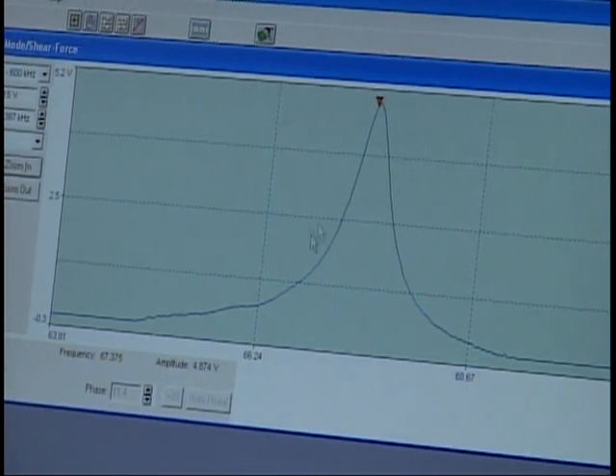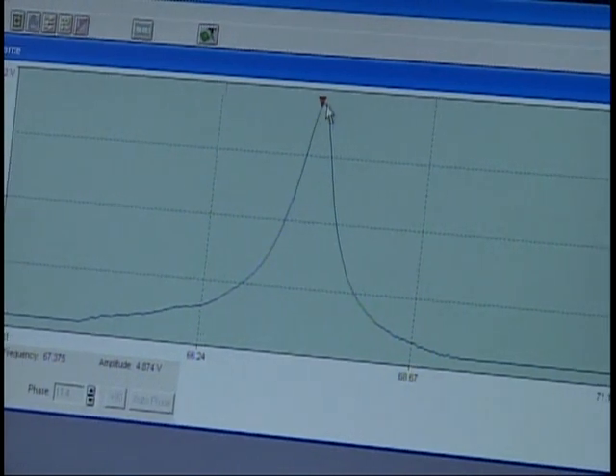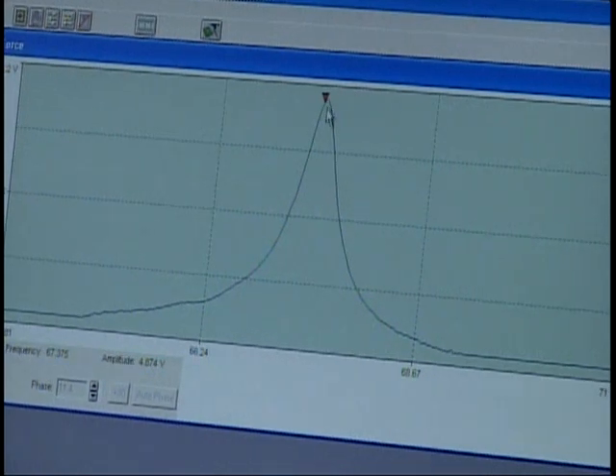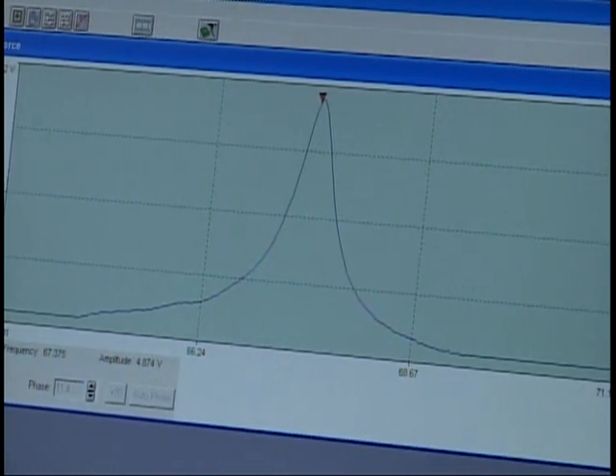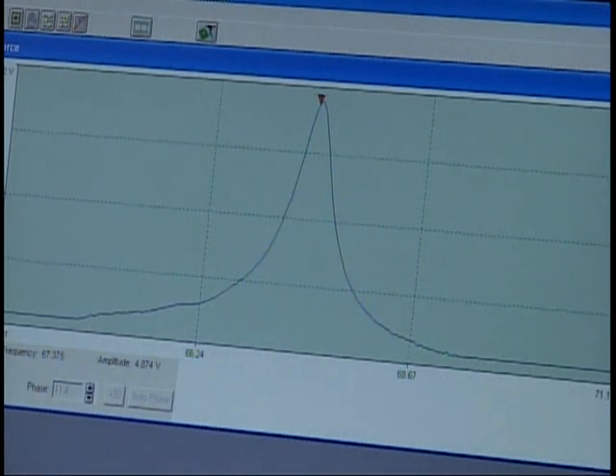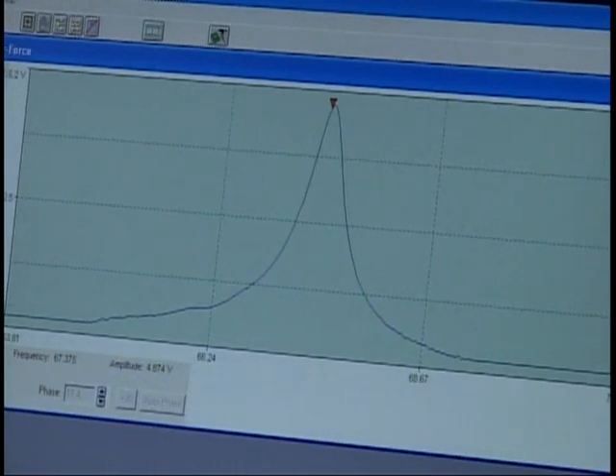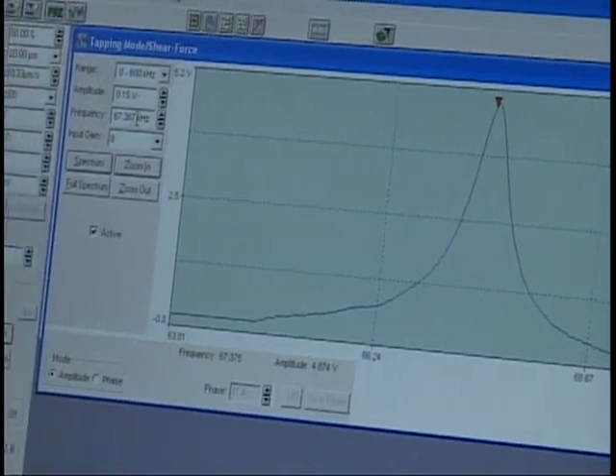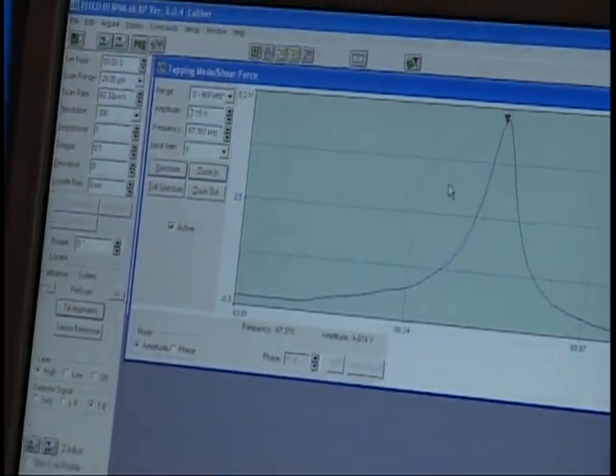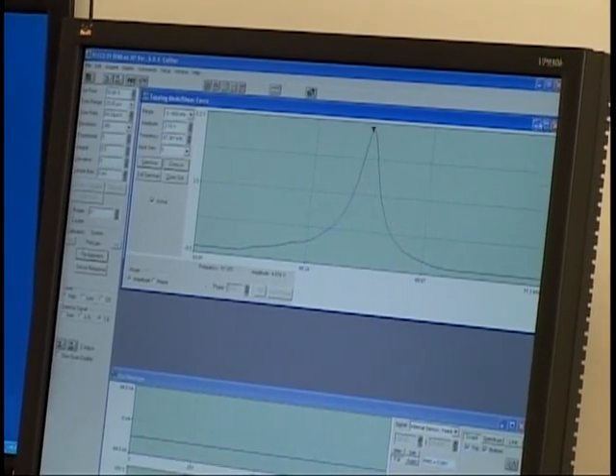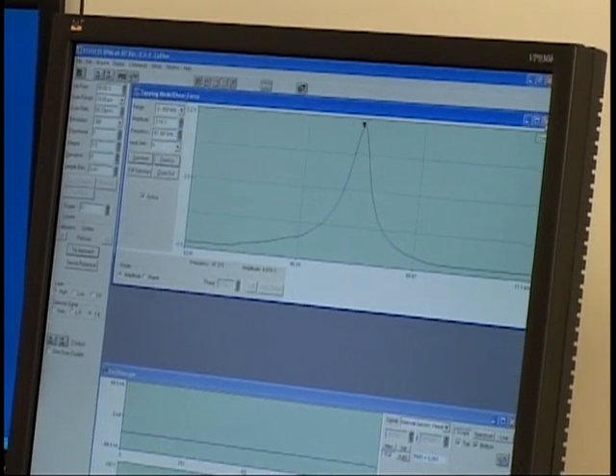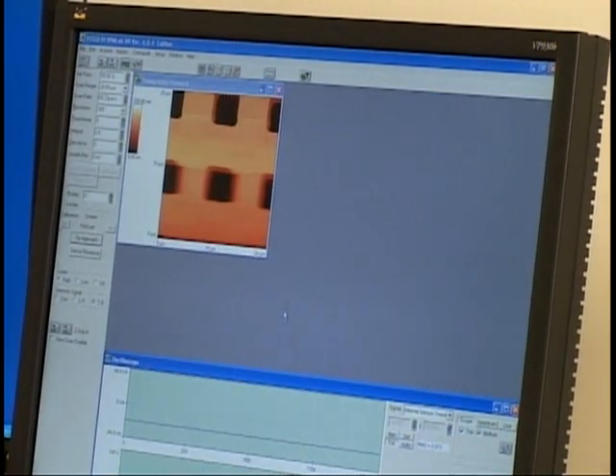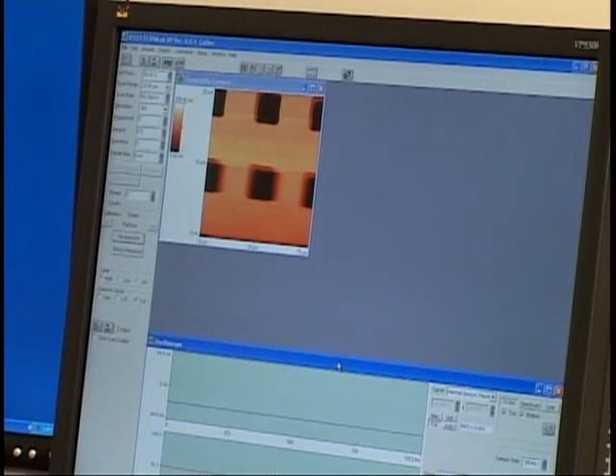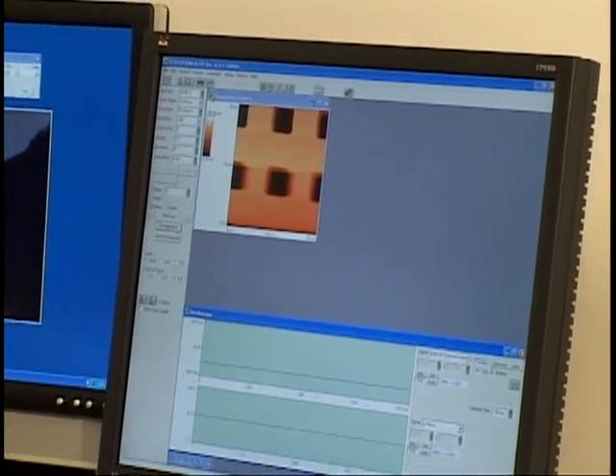So once you've selected your frequency, right now with the red triangle, you'll see it's at 67.367 kilohertz. And for this type of probe, it's usually between 50 and 100 kilohertz, which is right around the right range of this one. So we know that this is the right peak. So once we select our frequency, we want to minimize it. Don't close it, because closing will turn off tapping mode. So minimize it. It's down here.